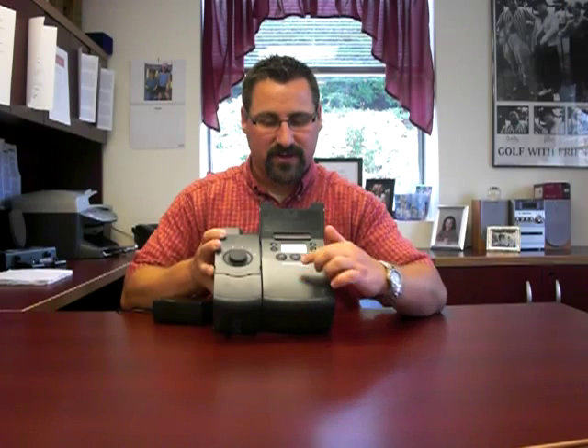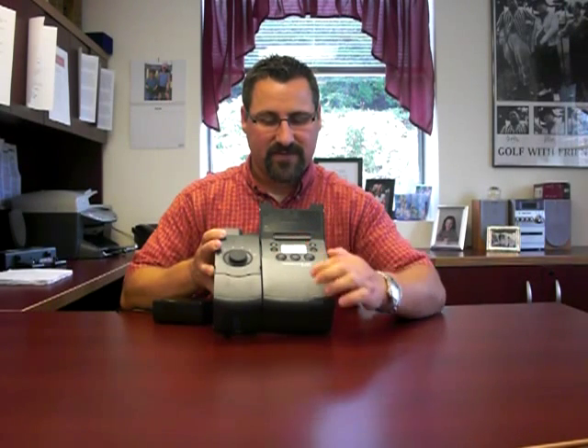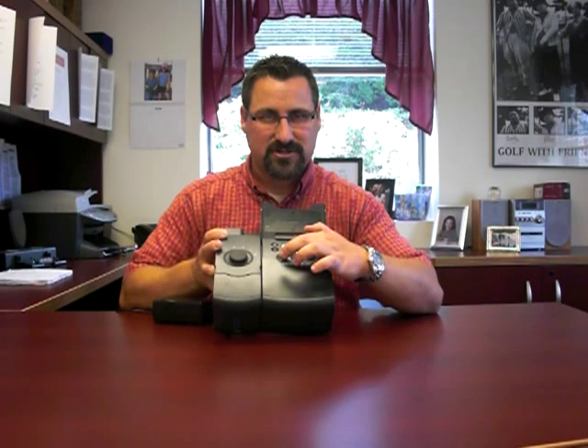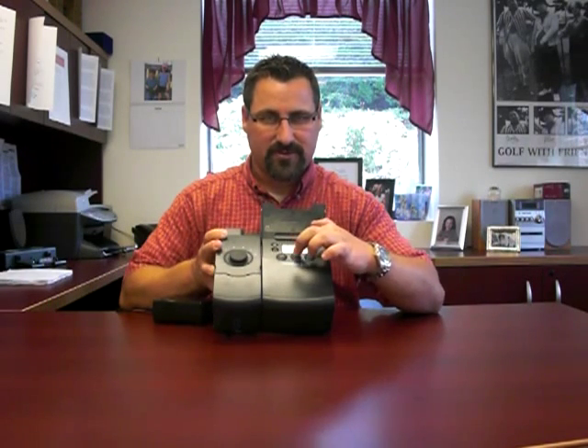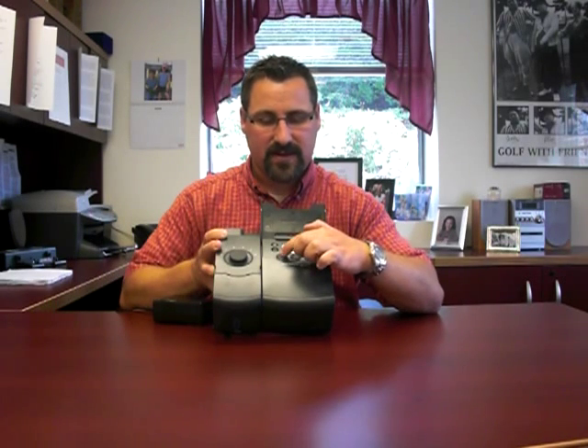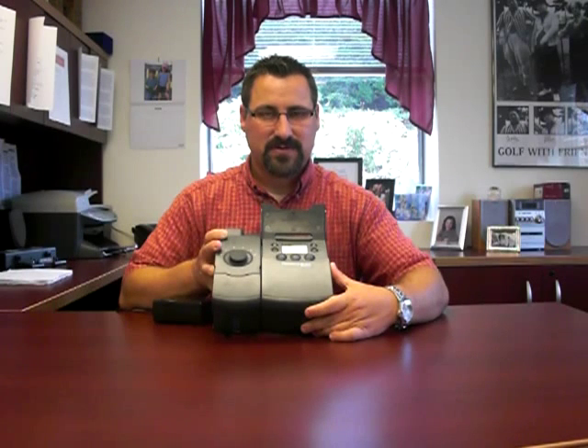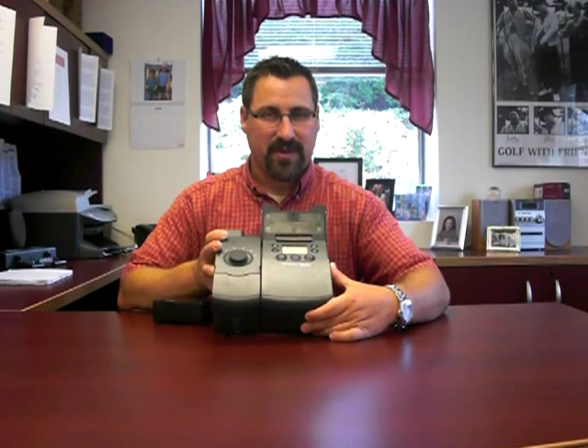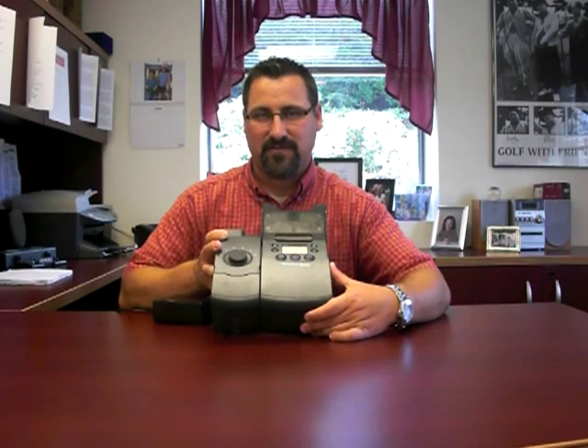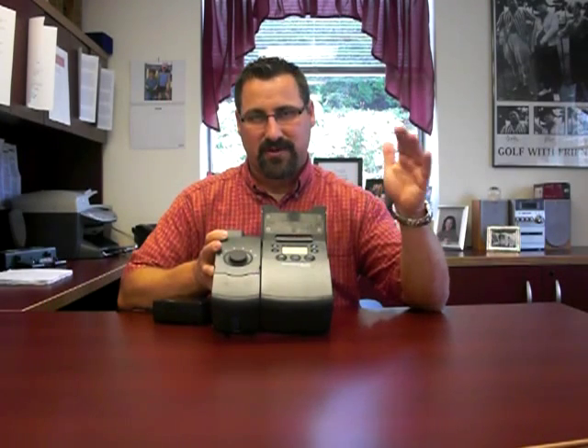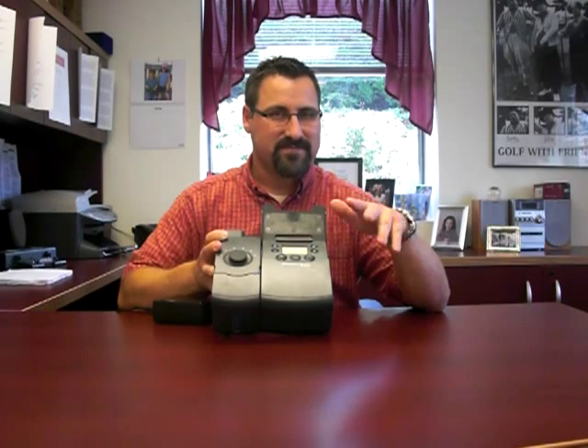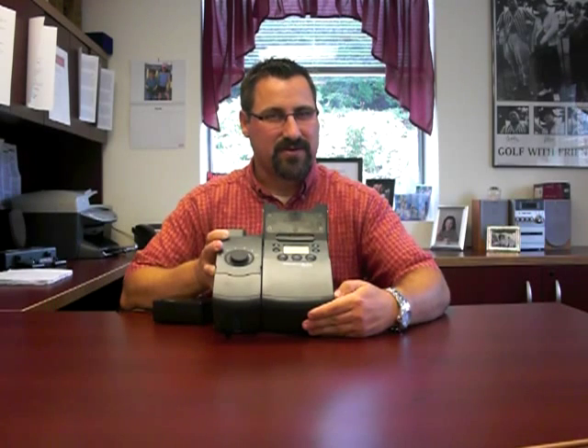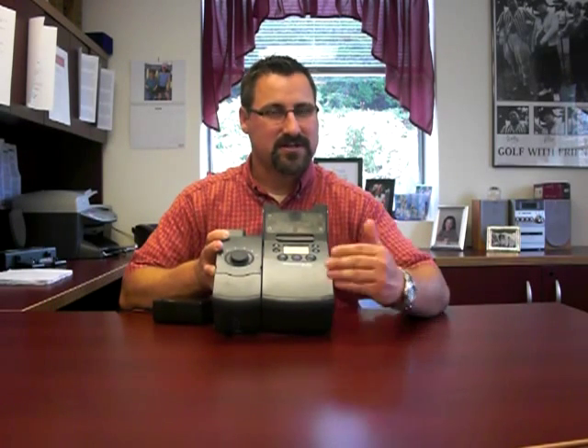Now probably the most important button on the machine is the button to the left, and that's the ramp button. What that allows you to do is when you first go to bed at night, you're going to turn your machine on, it comes on to the full pressure, then immediately hit that ramp button. What that will do is cut the pressure down to a very, very low level, which means there's not as much air coming in through your mask, so the breathing will be a lot more comfortable and allow you to fall asleep easy. Your machine will start very low, and it'll gradually increase pressure very slowly over an approximate time period of, on average, around 20 minutes. So you'll have a 20-minute period where the pressure is not so much, allowing you to get used to the therapy.